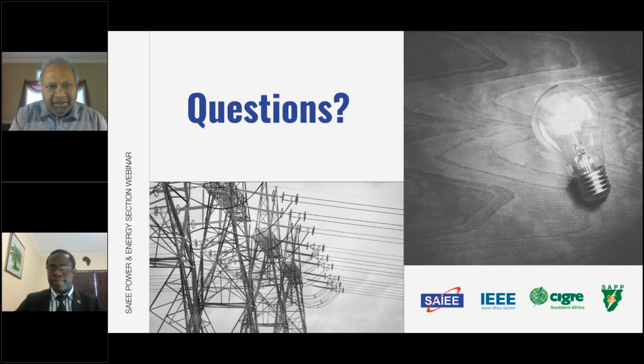I'll give you my grid level perspective. I'm not a harmonics expert, but I know these are introducing all kinds of new frequencies and harmonics into the grid, and they typically localize, like at a wind plant or a solar plant where you have inverters. From the grid level perspective, the explosion of power electronic loads is an issue. In the old days, loads gave you support during emergencies, meaning when the voltage went down or frequency went down, the load went down. But with power electronic loads, they do not go down, they're constant power. So from the grid operator's perspective, the proliferation of power electronic loads is not helping them.